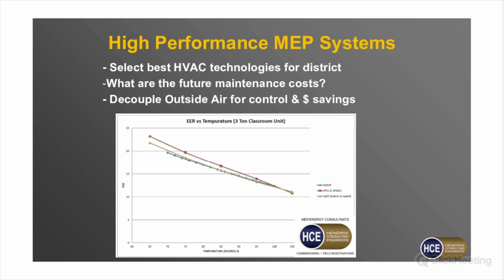But you'll notice that's the same thing for a 2-speed rooftop, which is the red line, and the green line, which is a traditional split system, also in a 2-speed. So as the air temperature goes up for the air-cooled equipment, their efficiency goes down. As the air temperature gets cooler, the efficiencies go up, just like the water temperatures for the water source stuff. So you've got similar things.